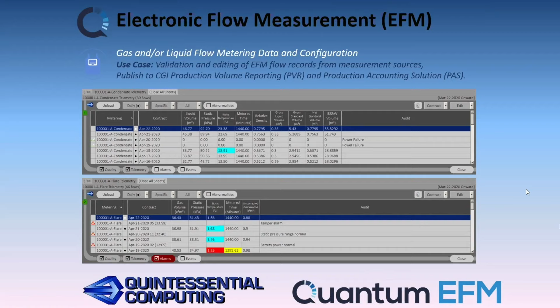For production volume reporting on SCADA projects, we often see requirements to move a random piece of analog data from the SCADA system all the way up to the production accounting systems. Process value reporting essentially allows us to do that. It's similar in concept to an OPC tag, in that you can pull a history from a data source. We can go after OPC tags or the VTScada historian, pull in this information, and organize it for downstream publishing.